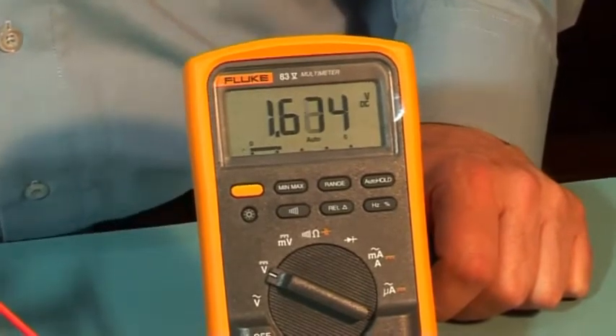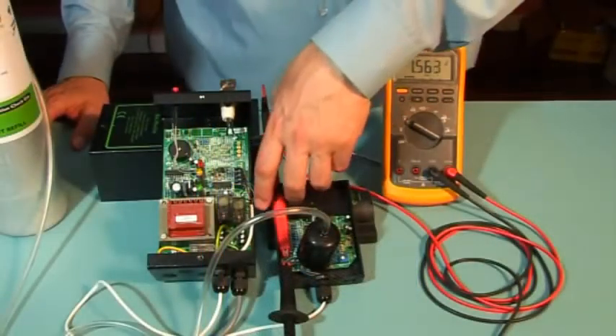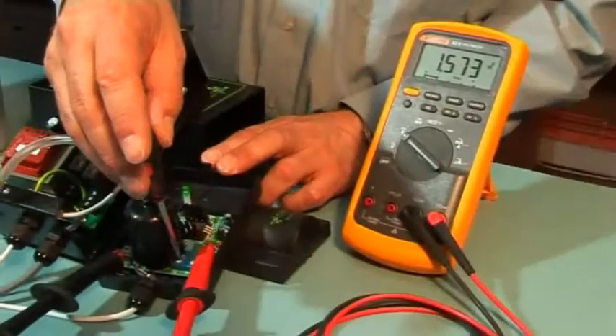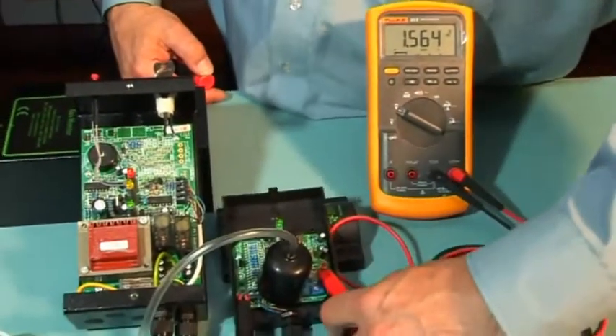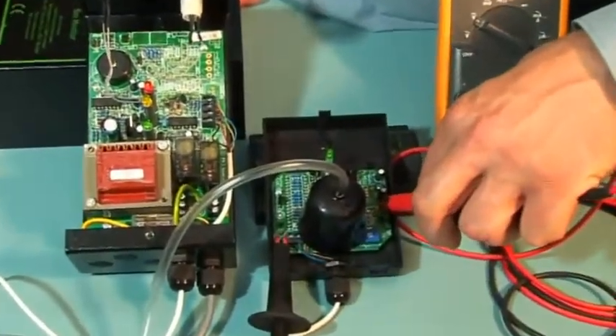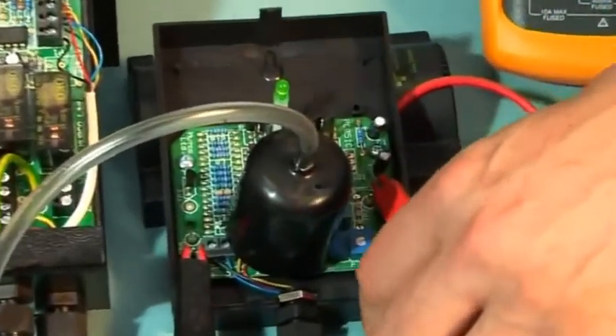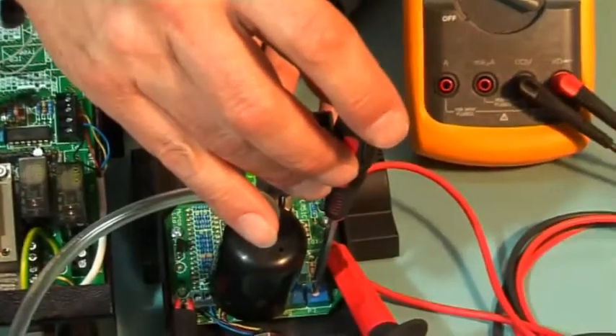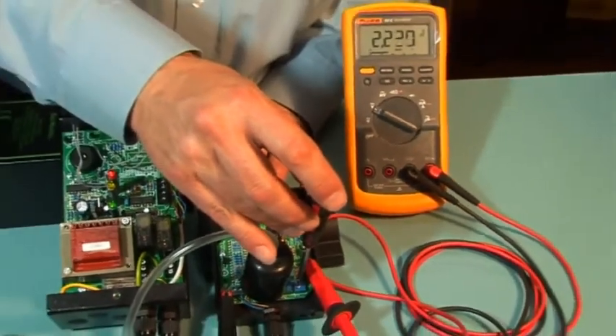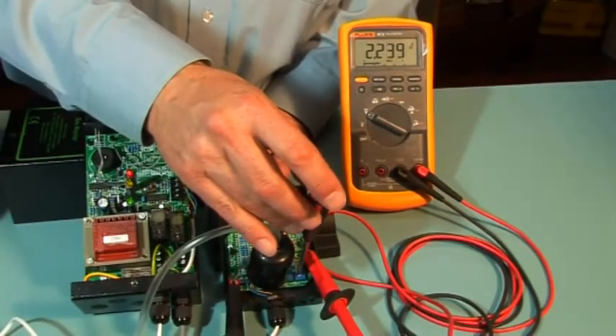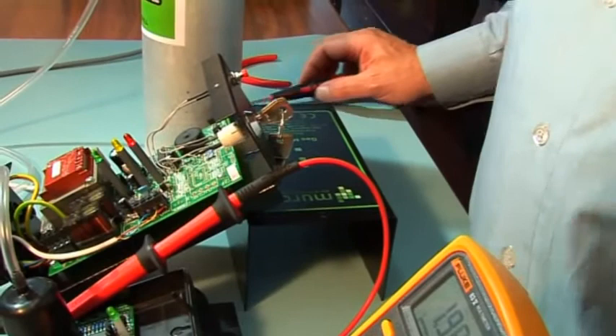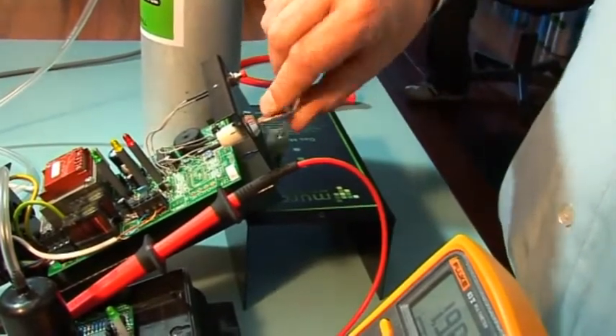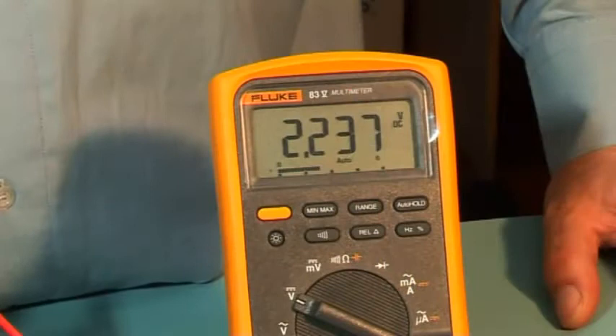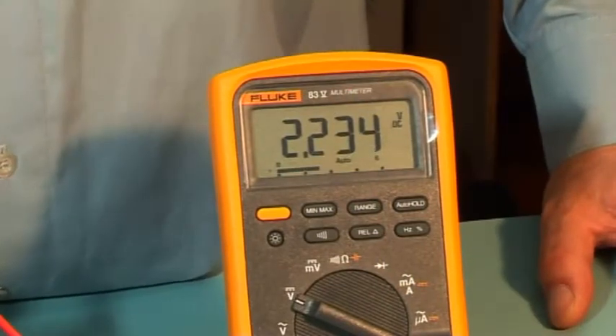For the first recorded voltage, monitor between TP5 and TP2 and adjust P8 to the recorded voltage. Then, moving the positive lead from TP2 to TP1, adjust P7 to approximately 50 millivolts below the second recorded voltage. The MGD will now be in alarm and relays should activate. The sounder can be silenced by turning the key switch. Remove the gas and the unit will come out of alarm and return to its normal voltage of 0.3 volts, or as the settings on the rating label.